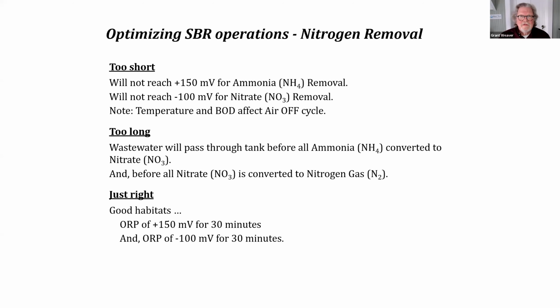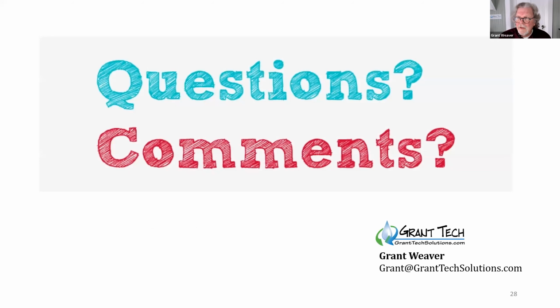My message here is, if you're running an SBR and you're getting pretty good nitrogen removal, you might be able to get better if you periodically, and I don't mean every week, every few months, consider changing your cycles based on seasonality. Of course, they have built into these systems storm flow modes, which are really aimed to protect the solids as much as anything. Any questions on that?